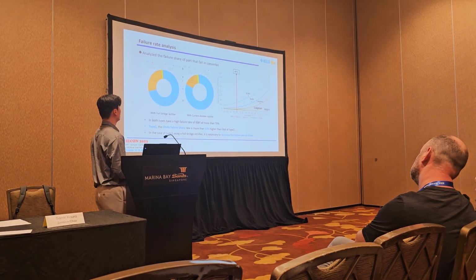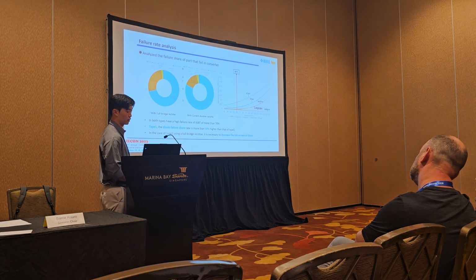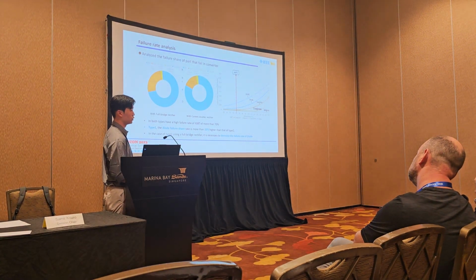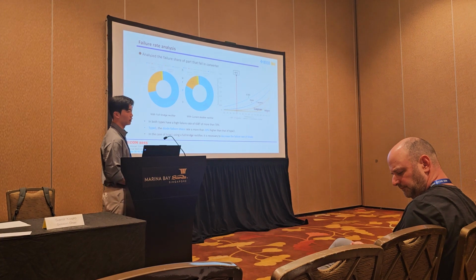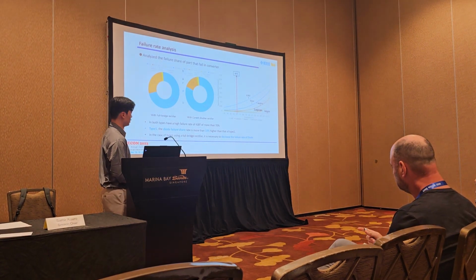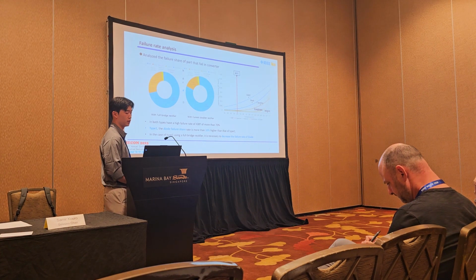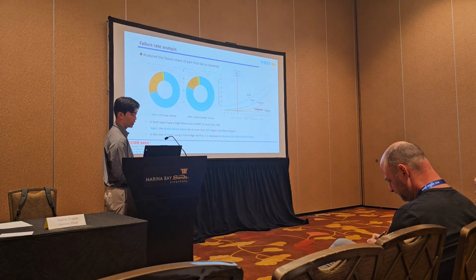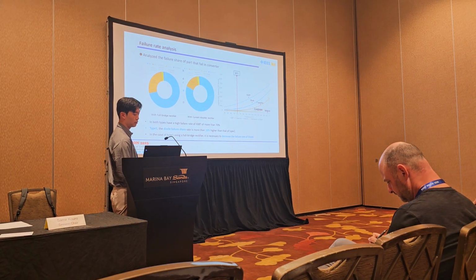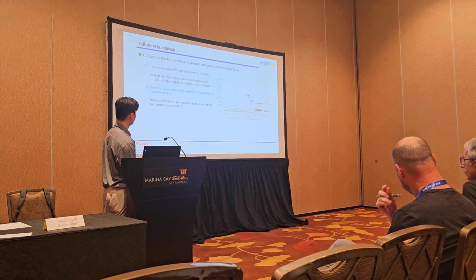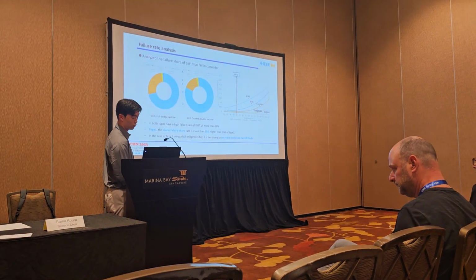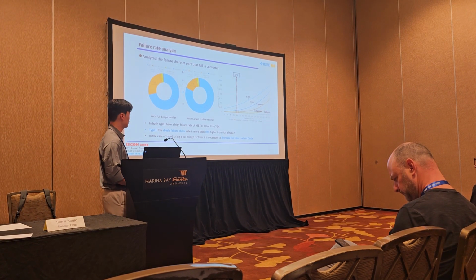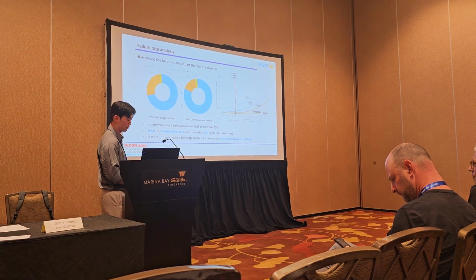Additionally, we analyzed the failure share of each part in the converter at 65 degrees. The blue section is the IGBT failure share, and the orange section is the diode failure share. From this, both types have a high IGBT failure share of more than 70%. In the case of type 1, the diode failure share is more than 10% higher than that of type 2. So, it means type 1 needs to decrease the failure rate of the diode.